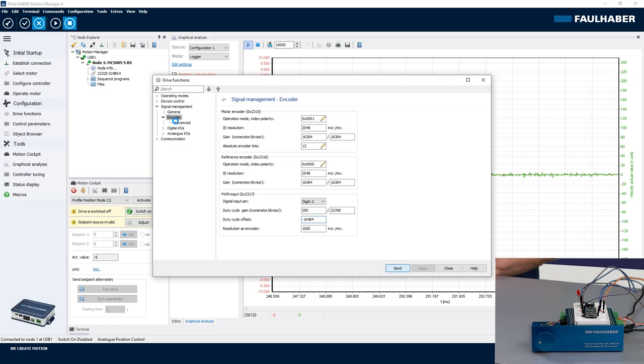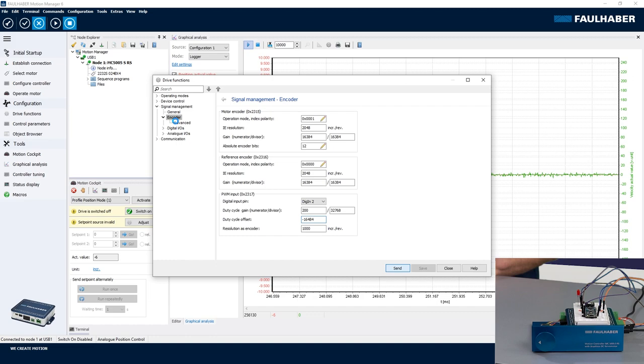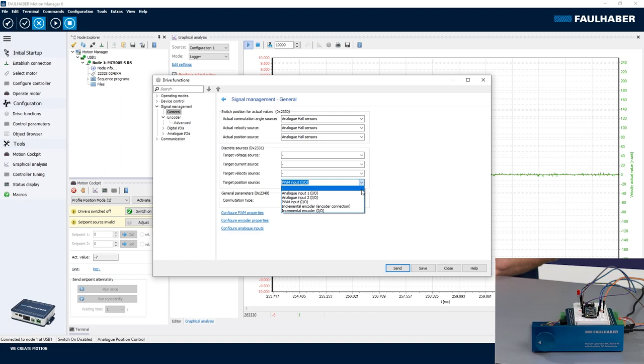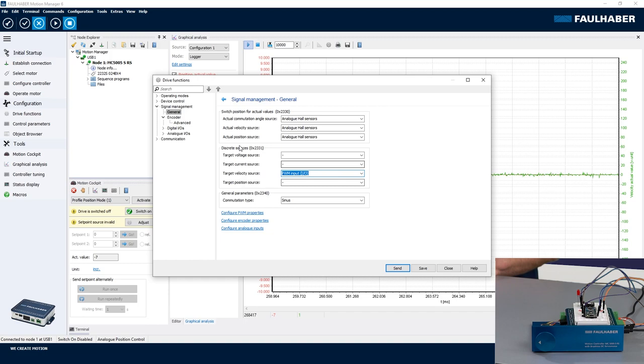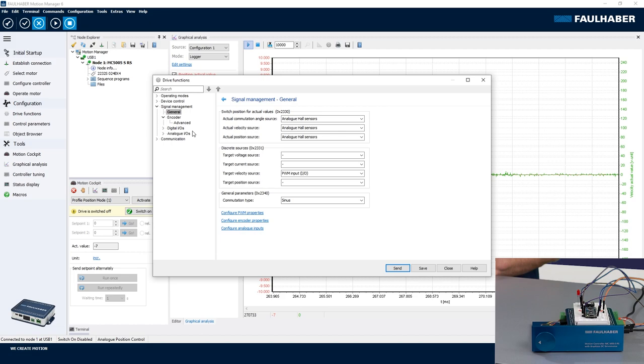Okay, so scaling is done. I have to change the routing, so no longer using the PWM input as the target position but as the target speed. And change to speed control, that's done up here in the operating modes. And this is analog velocity control. Send and, of course, remember to save your settings if you want to have them permanent.